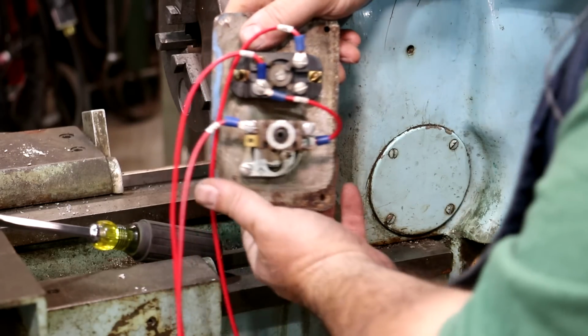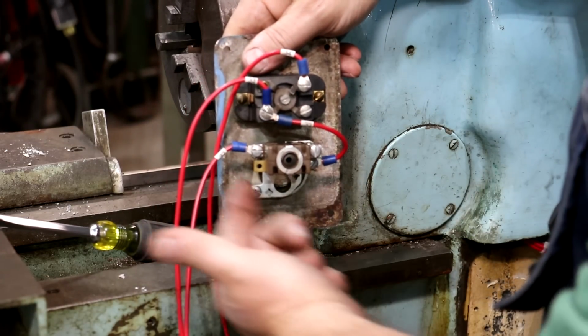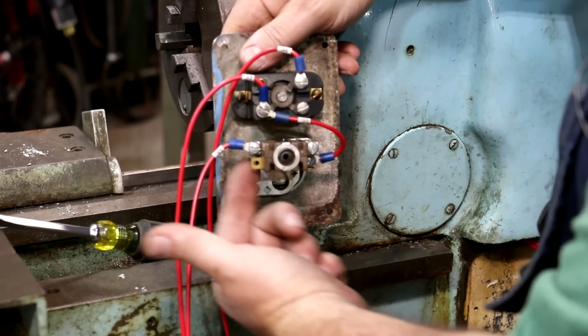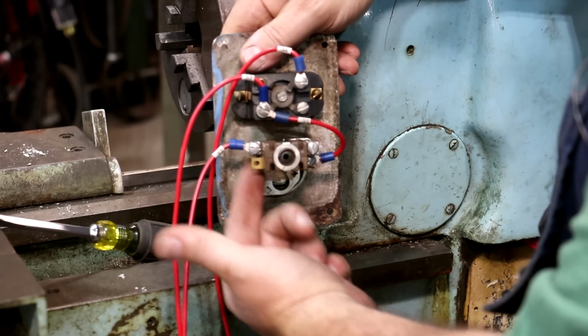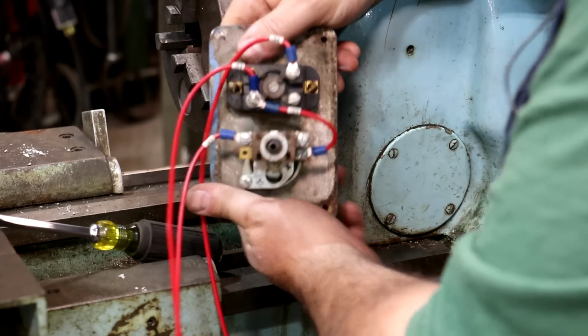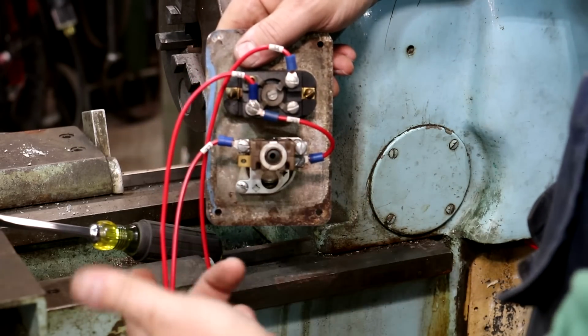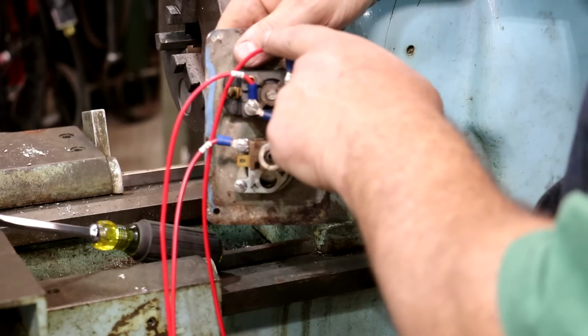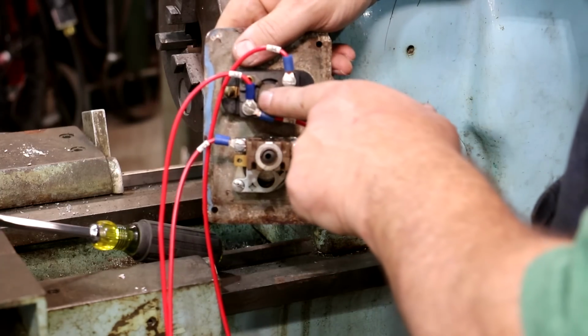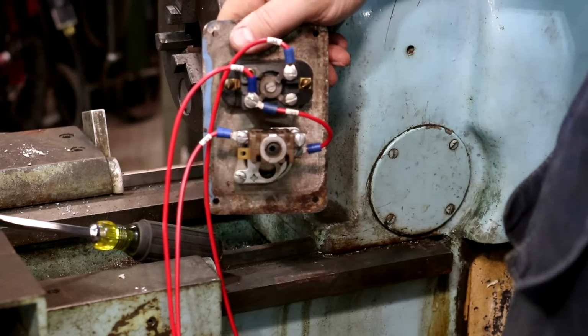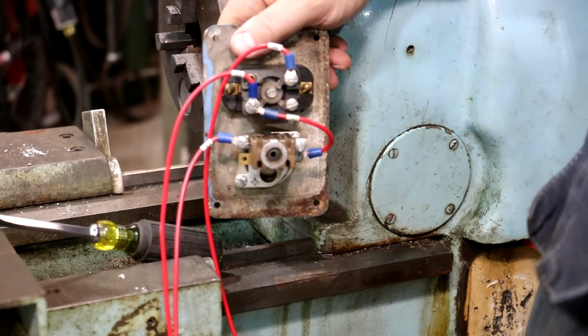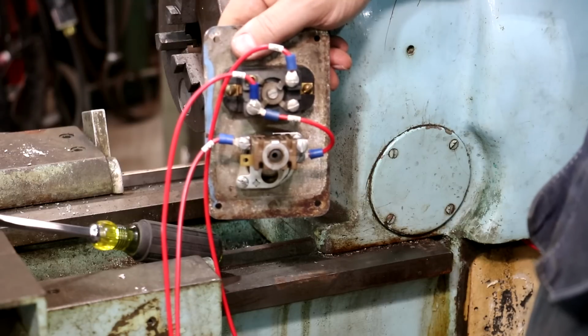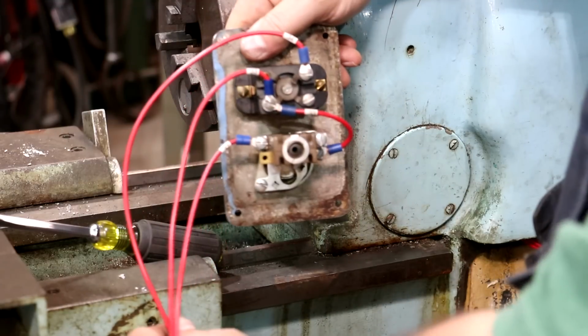Now to turn it off, we push this button. Again, this button normally has a closed circuit, so power is going through it. Whenever we push the bottom button, it opens that circuit, the circuit collapses, and no power goes through here. Now we've got power coming up here, but until we push the start button again, it's not going to energize the system. Pretty basic control, basically 3 wires going to it.